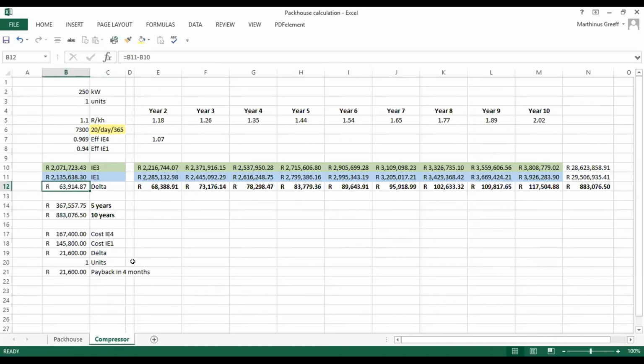I calculated the savings for that motor in one year would be just over 63,000 Rand per year. Looking at savings over 5 years, that would be 367,000 Rand, and over 10 years, a saving of about 800,000.